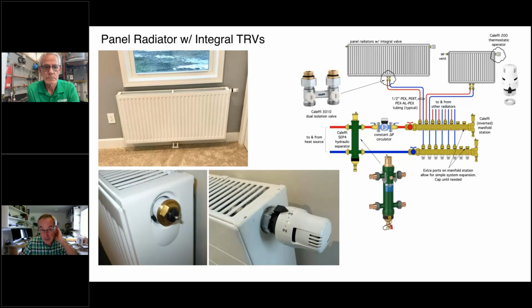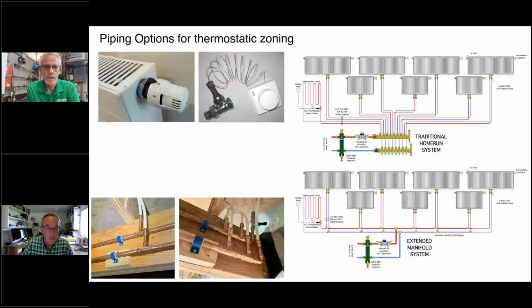You can also get thermostatic control valves that have a capillary tube and a wall knob. If somebody can't necessarily bend over, if you have a low profile heat emitter and this operator is 10 inches off the floor, some people just aren't able to bend over to operate that. So you can do this. This capillary tube is 2 meters long, so it's a little over 6 feet long. This is not a wire.